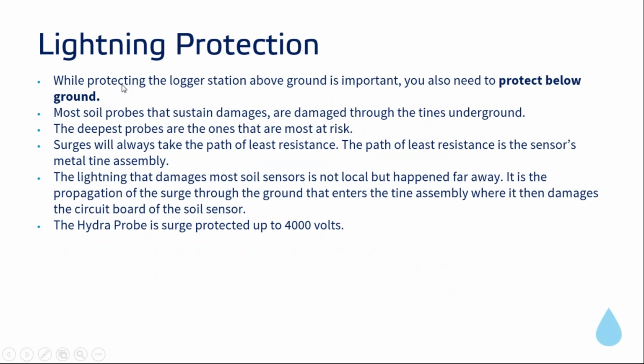And so, we can protect the logger station above ground, but it's also important to protect it below ground. And the point of this slide here is the earth ground transient, or the surge that propagates through the ground, is really what damages the probe. The voltage surge will be propagating through the ground. It'll see the tine assembly, or the metal part of the soil sensor, and it'll get in there and wreck the circuit board. And surges will take the path of least resistance.